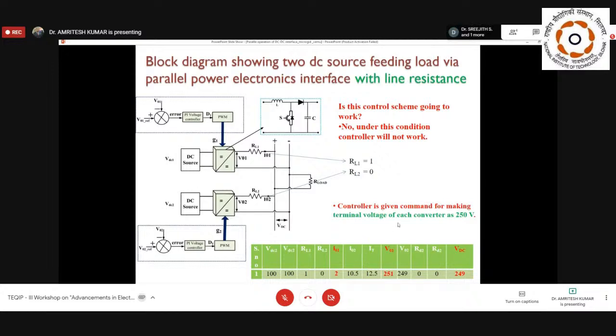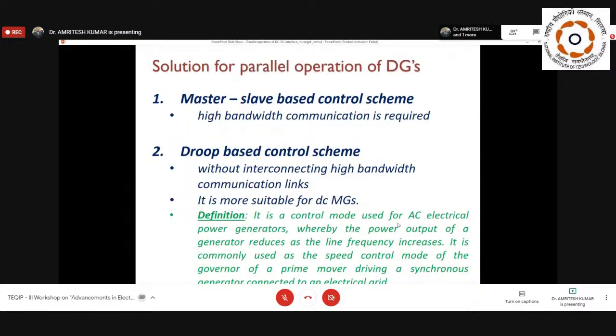So what is the solution? There are many approaches. The major approaches are based on a master-slave control scheme. In the master-slave scheme, one source is made the master and the other sources are slaves. Like in a normal power system, we treat the grid as master, and whatever DC sources there are, like photovoltaic, wind and battery, are in slave mode. The master takes the role of voltage source, maintaining the voltage at the common DC grid or the PCC, and the slave respects that and is always in current control mode.